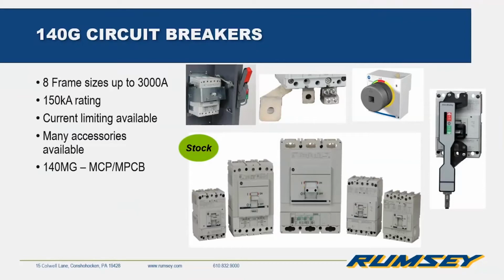And for specific motor load applications, there's a 140MG. So if you're familiar with the 140Ms, they go up to about 45 amps. And then the 140MGs will take over from there and go all the way up to 1200 amps for motor applications.